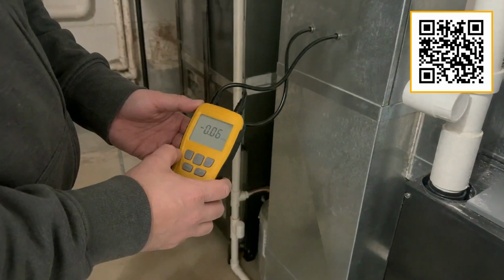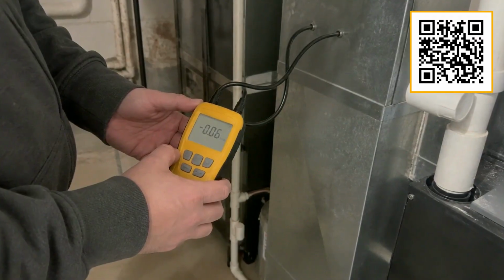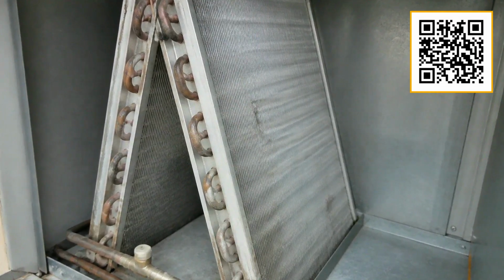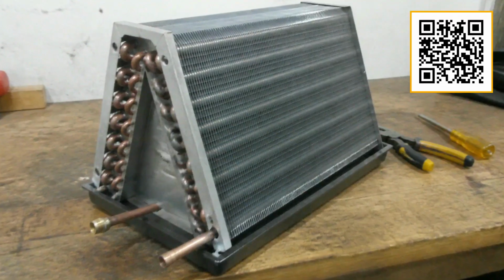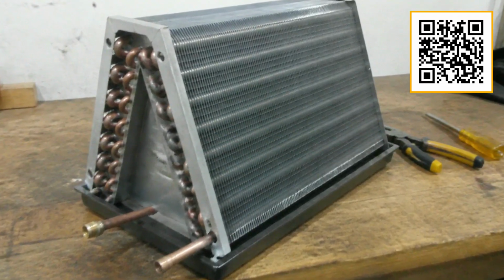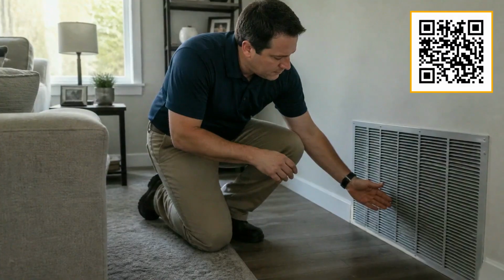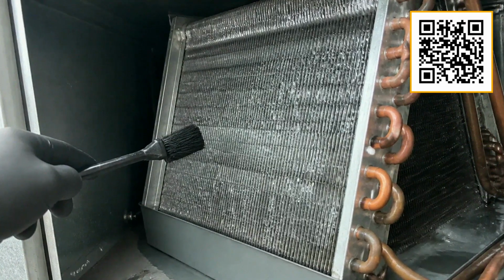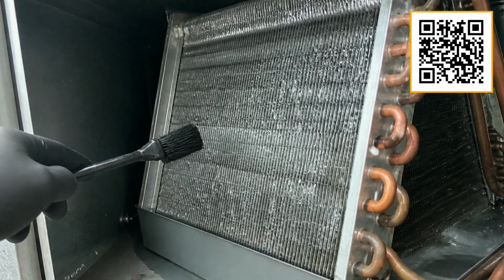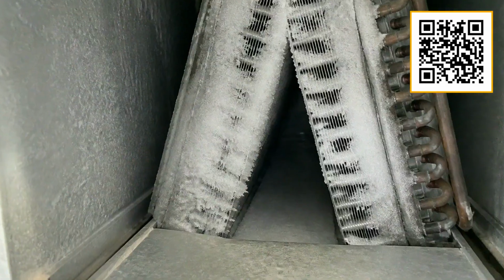When static pressure goes up, airflow over your evaporator coil slows down. That coil is the part of your AC that actually absorbs heat from your home's air. It relies on a steady, sufficient volume of air moving across its surface. When airflow drops, the coil gets colder than it should. It can ice over. A frozen evaporator coil cannot do its job. The system loses its ability to cool.